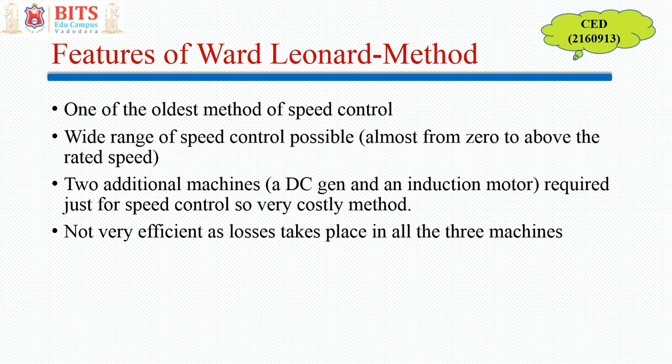However, two additional machines are required just to achieve speed control of the DC motor — an additional DC generator and an induction motor. So this is a very costly method. Efficiency is also lower because losses occur in all three machines. It is a very inefficient and costly method, used only when speed variation was absolutely essential and cost was not an issue. This is an obsolete method — this is not what we use these days.